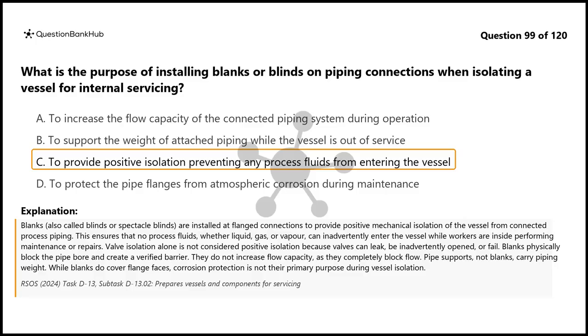They do not increase flow capacity, as they completely block flow. Pipe supports, not blanks, carry piping weight. While blanks do cover flange faces, corrosion protection is not their primary purpose during vessel isolation.